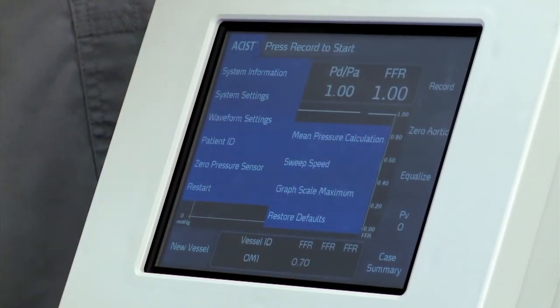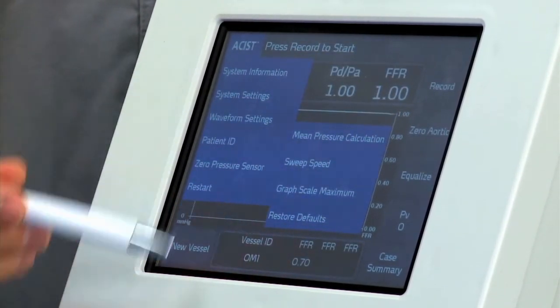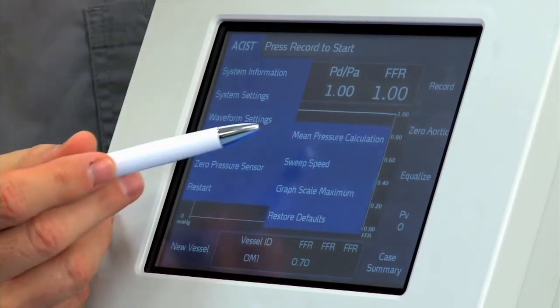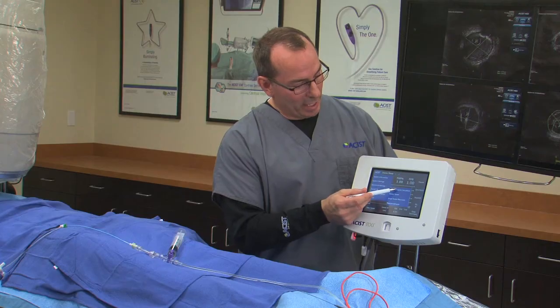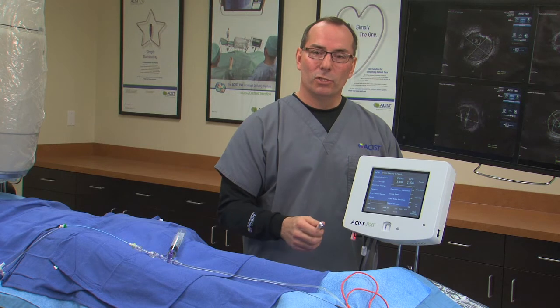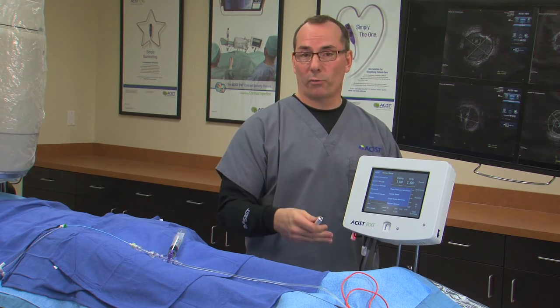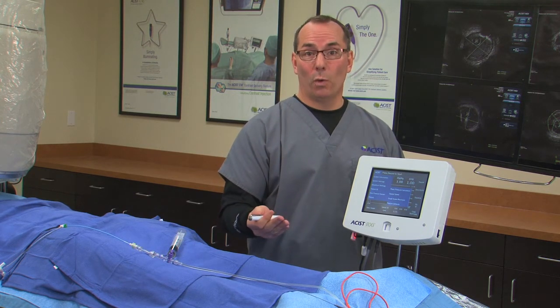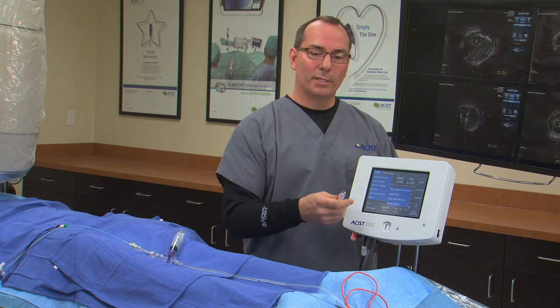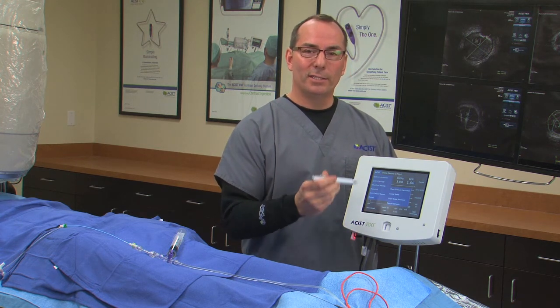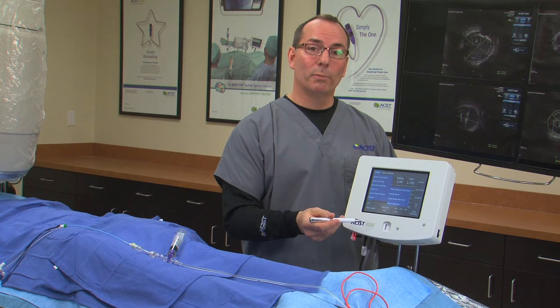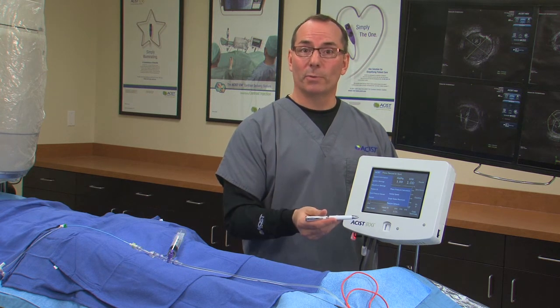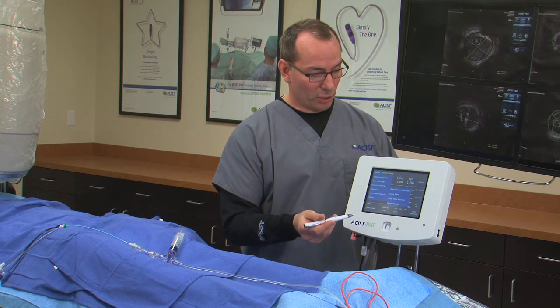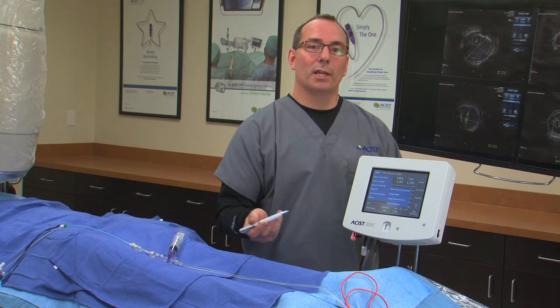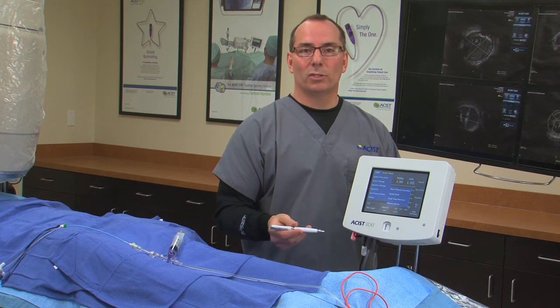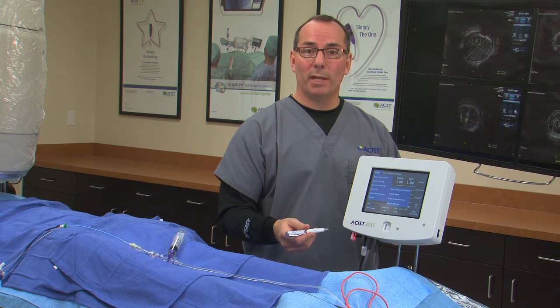Underneath pressure waveform settings, we are able to change how the pressure waveforms look on our screen. We can set the mean pressure calculation to 1 or 3 or 4 or 8 or 12 beats. So essentially what that is, is that this system will calculate a mean arterial pressure after the third beat. It defaults to 3. If the user is using IV adenosine and wants to go to 8 or 12 beat mean, they can do that.